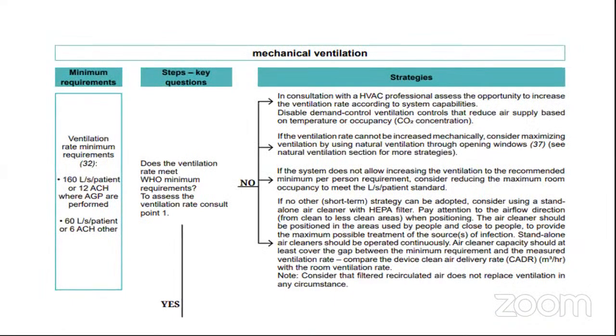Similarly, we have the mechanical ventilation strategies, which work on the same pattern. The requirements remain the same, and the steps remain the same. Only the strategies change, because there we will need the assistance of the HVAC person, who has to disable the demand control ventilation controls to reduce the air supply. Now, if the ventilation rate cannot be increased mechanically, then we may have to go ahead with the natural ventilation system.